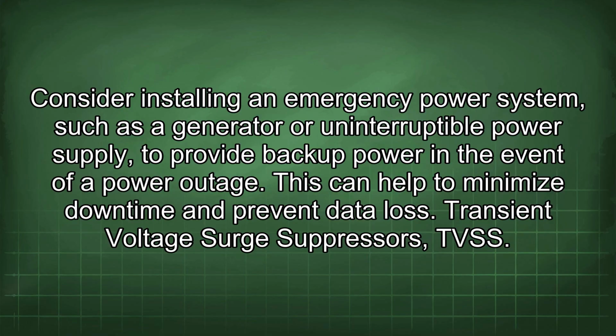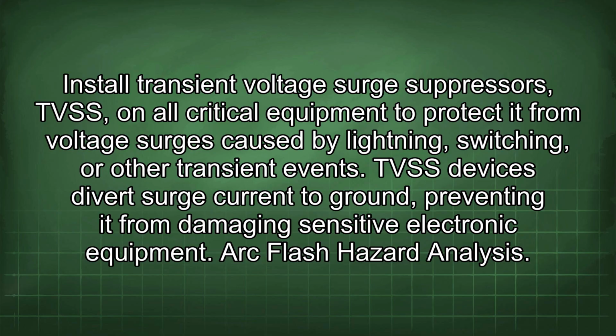Transient voltage surge suppressors, TVSS. Install transient voltage surge suppressors, TVSS, on all critical equipment to protect it from voltage surges caused by lightning, switching, or other transient events. TVSS devices divert surge current to ground, preventing it from damaging sensitive electronic equipment.